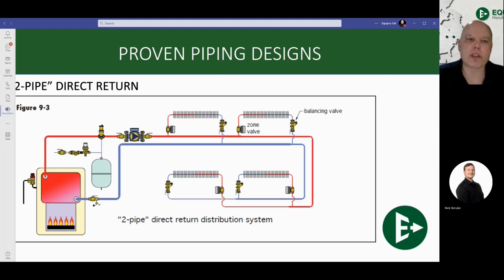Moving down the line here, we're going to have what's called a direct return. This is where all of our rads for the first time are going to see the same water temperature being sent to each rad. Because we have our own individual supply line and our own individual return line, where we have all the hot sides coming off of the supply, and then it isn't until the last rad that we start to have the return coming back and catching all these returns on the way back. Now this makes a whole lot of sense, as we don't need to oversize our rads anymore. Each rad is going to see the same temperature, but it becomes a little bit cumbersome with regards to the amount of piping that is going to be required.